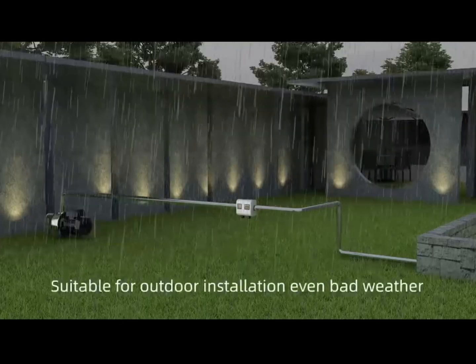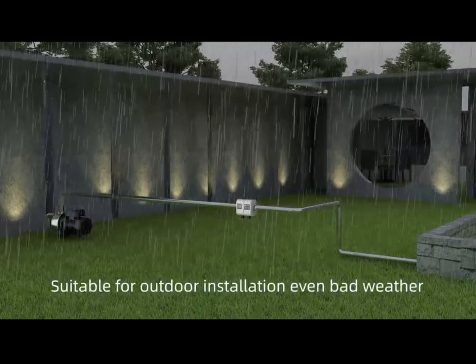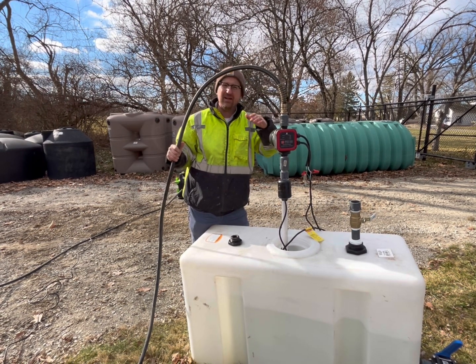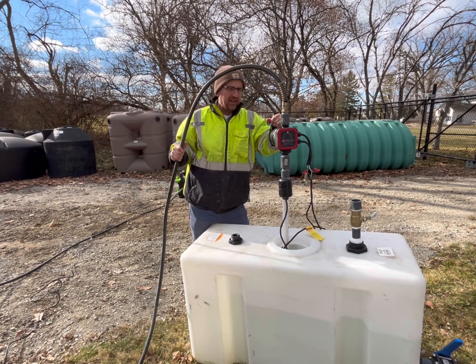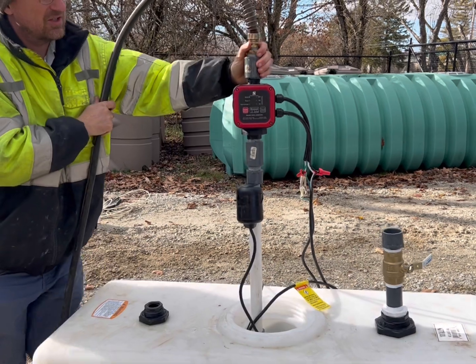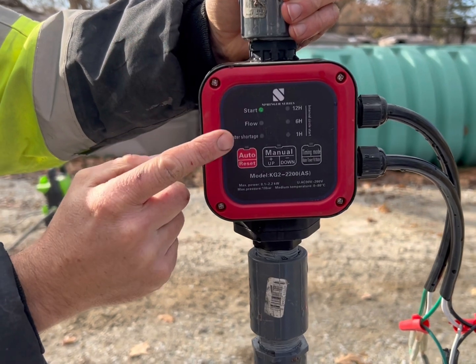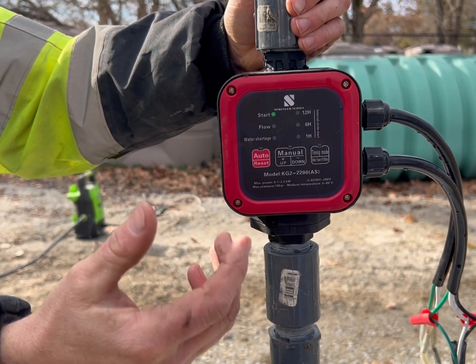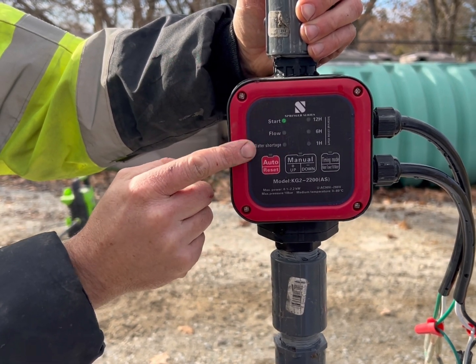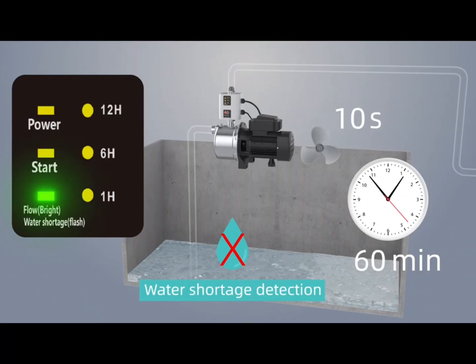This Springer Series Automatic Pump Controller is completely waterproof. It can be stored outside — you would want to protect it from freezing weather, but it can be exposed to the elements otherwise. It has a display on the front. You have your start light right here that will always be illuminated if it's getting power. You have your flow light, which will turn on when it's calling for the pump to turn on. And then you have your water shortage light.